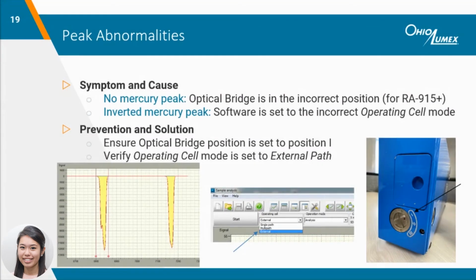No mercury readings or inverted peaks are typically an indicator the analyzer is not set to the correct parameters for using the external attachment. These specific peak abnormalities are usually caught when initially trying to calibrate. Ensure the optical bridge position on the back of the spectrometer is set to position 1, and the operating cell mode on the Rapid software is set to external path prior to starting the graph. If inverted peaks are observed only while analyzing sorbent traps, this may be a sign there is an interferent. Stop analysis and call Ohio Lumex for further troubleshooting.